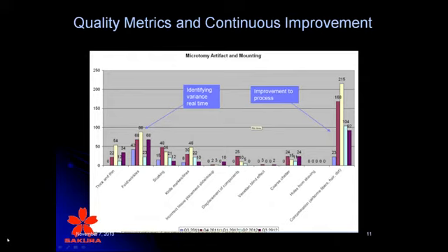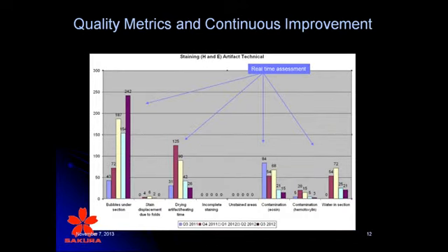For instance here, folds and wrinkles and contamination. You wouldn't believe the contamination that you see in digital pathology underneath the cover slips. Even the cleanest cover slip, I have to tell you, I've tried 7 to 8 vendors for cover slips, and I've still to find a vendor that does not have hair or airborne fibers or any type of dirt within their cover slips.